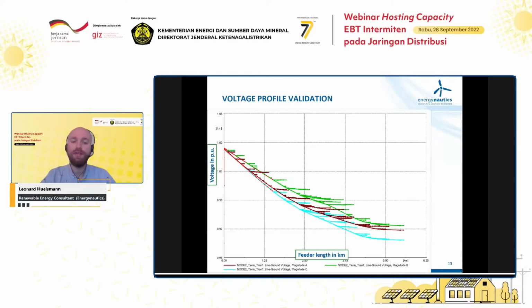Now, in order to look at the impact of your distributed generation, what we can look at is the voltage profile. This generally shows a certain distribution feeder with the primary substation located here, and we see the length of the distribution feeder, and you see what the voltage will be in your distribution network along this entire distribution feeder. The further you are away from the primary substation, typically the lower your voltage is during times where you have a lot of load in your network.